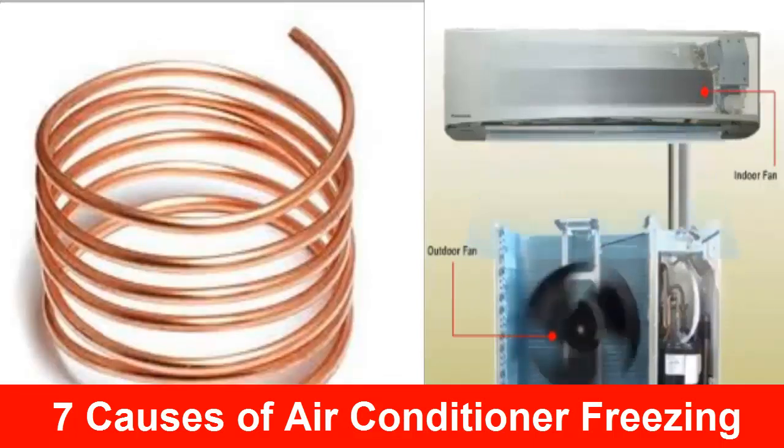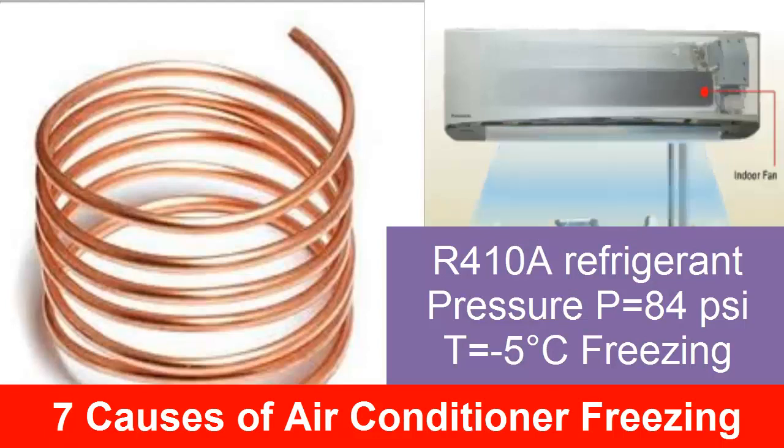5. Obstruction of the capillary tube. If the capillary tube is obstructed, the refrigerant will not be able to circulate properly, which can cause lower than normal pressures, causing the evaporator to freeze.